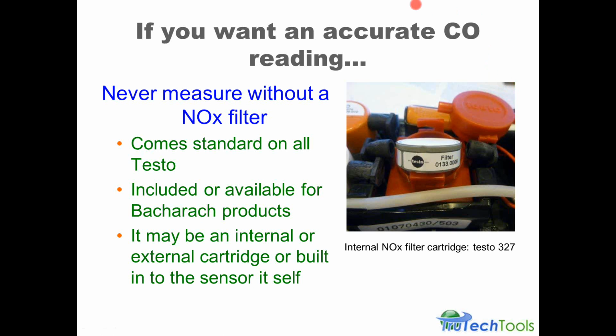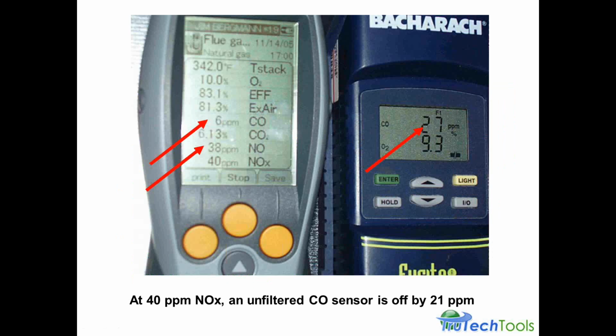And so our advice, if you want an accurate CO reading, never measure without a NOx filter. It comes standard on Testo products. It's included or available for all the Bacharach products and the other manufacturers out there. And it may be an internal sensor or an external cartridge built into the sensor. This illustration here shows the internal NOx filter cartridge on a Testo 327, but sometimes these filters are built into the sensor and not removable and not replaceable. But it's best to ask or check with the vendor you're buying them from, or check with the manufacturer's literature to find out if you do have a NOx filter. But it's strongly recommended you make sure it's present to make good in-stack CO readings.